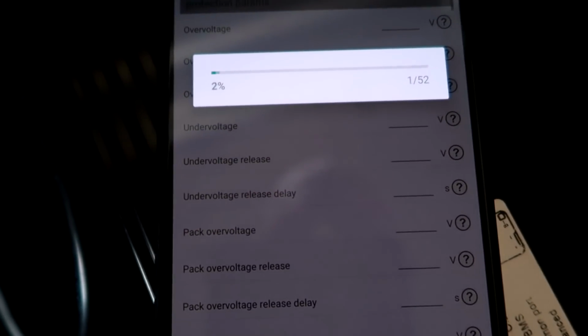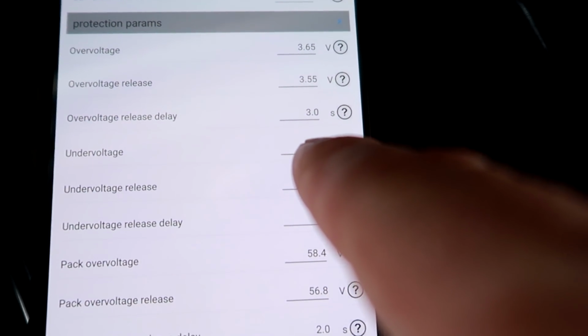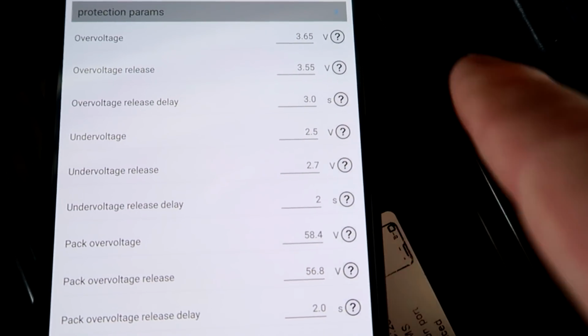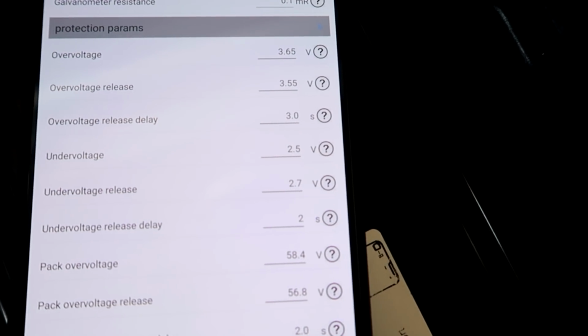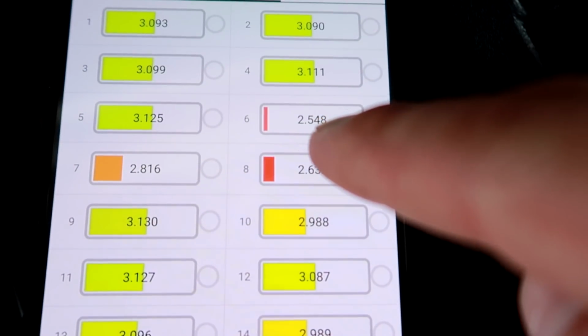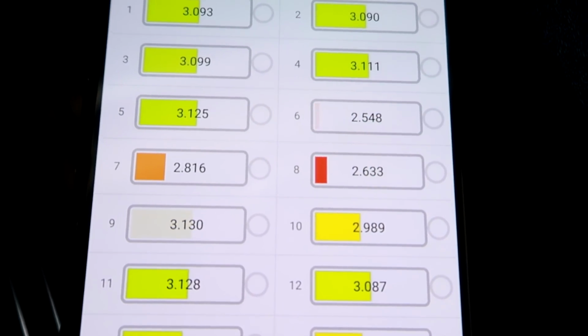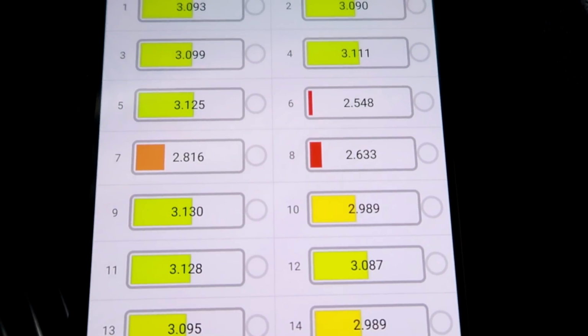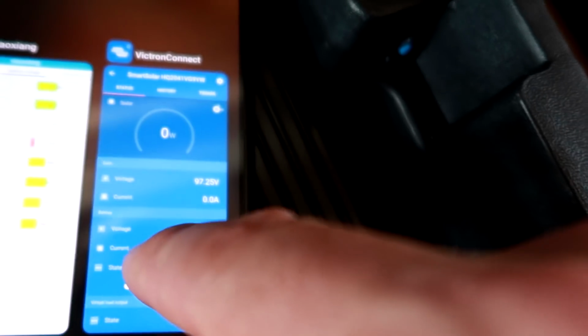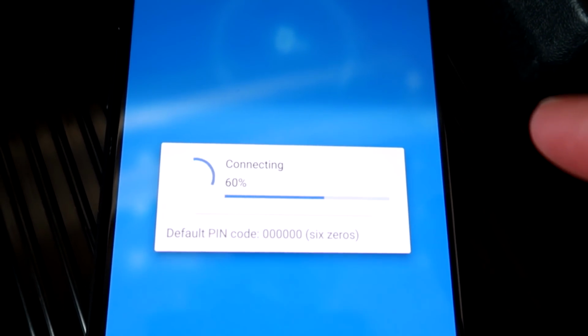I think it's 2.7 or so in the parameter settings. Yep, under voltage release is 2.7. So 2.5 triggers turn off, and at 2.7 the relay will turn on again. It will wait until this cell is at 2.7, and then it turns the BMS back on. Alright, let's turn on the charger.